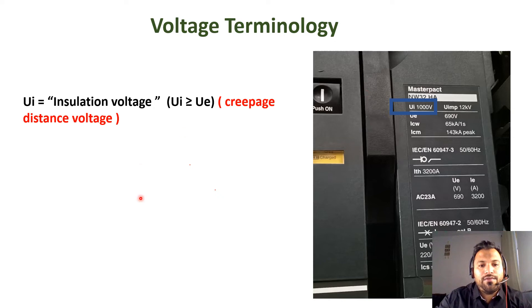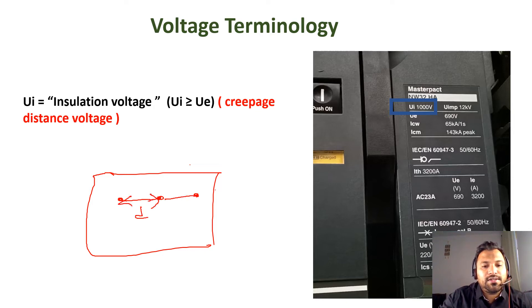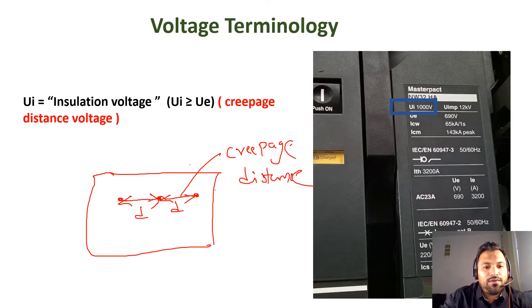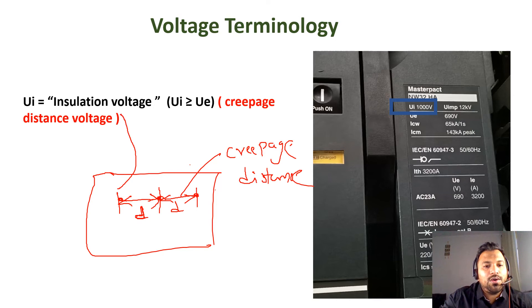Let me explain the Ui value with a simple concept. Inside the circuit breaker, there are terminals, and between those terminals a certain distance must be maintained — this is called the creepage distance. When a certain amount of voltage is applied across this distance and the insulation remains intact with no malfunction, the voltage at which this holds is called the insulation voltage or creepage distance voltage. This value is determined from that physical distance.